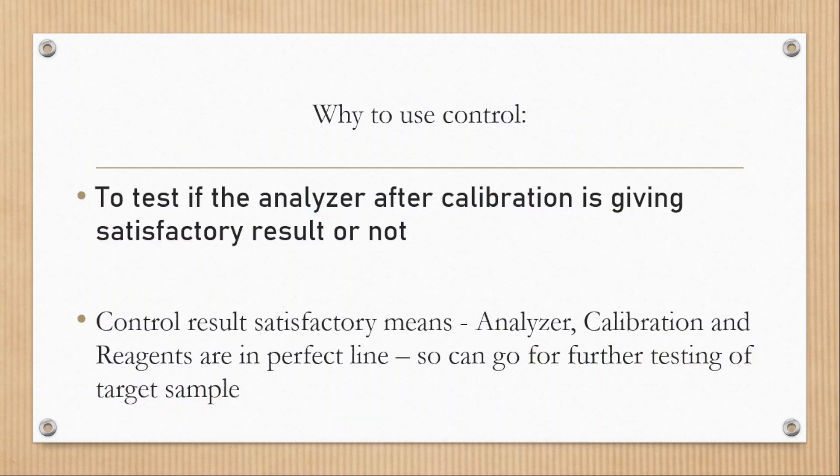Why to use control? To test if analyzer after calibration is giving satisfactory result or not. Control result satisfactory means analyzer calibration and reagent are in perfect line.